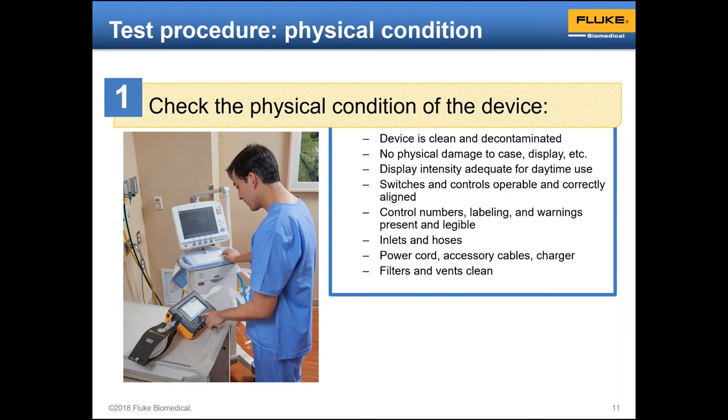Or they might be designed for portable use, like in an ambulance or in an aircraft. In those cases, a lot of times they're going to be operated on battery. If there are any filters or vents, we want to make sure that those are clean. So all of this physical inspection is always part of what we're going to do, even if all we're doing is electrical safety.